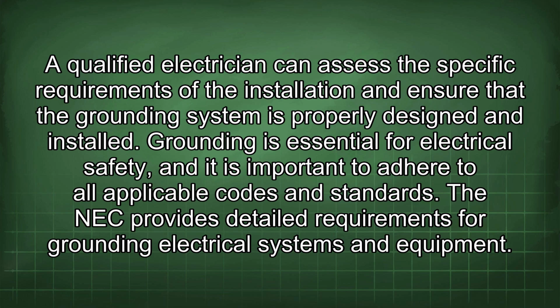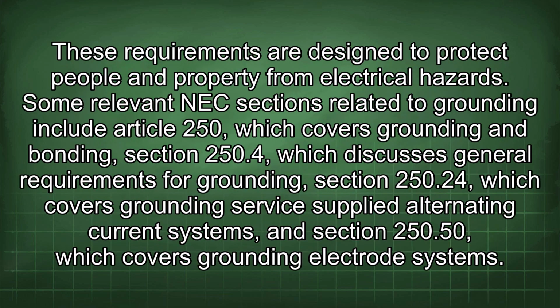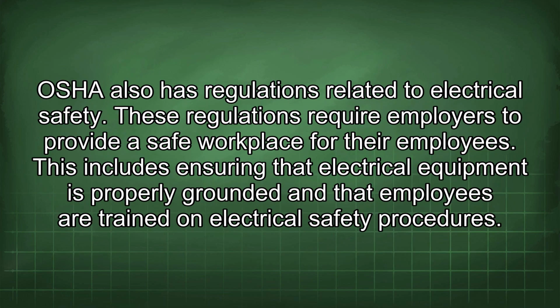The NEC provides detailed requirements for grounding electrical systems and equipment. These requirements are designed to protect people and property from electrical hazards. Some relevant NEC sections related to grounding include Article 250, which covers grounding and bonding, Section 250.4, which discusses general requirements for grounding, Section 250.24, which covers grounding service supplied alternating current systems, and Section 250.50, which covers grounding electrode systems. OSHA also has regulations related to electrical safety.